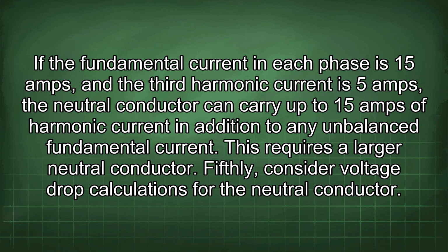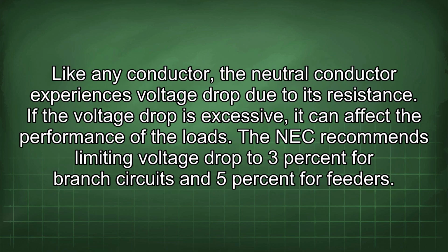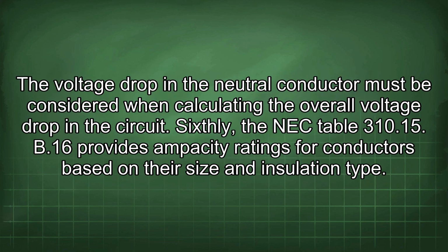Fifthly, consider voltage drop calculations for the neutral conductor. Like any conductor, the neutral conductor experiences voltage drop due to its resistance. If the voltage drop is excessive, it can affect the performance of the loads. The NEC recommends limiting voltage drop to 3% for branch circuits and 5% for feeders. The voltage drop in the neutral conductor must be considered when calculating the overall voltage drop in the circuit.